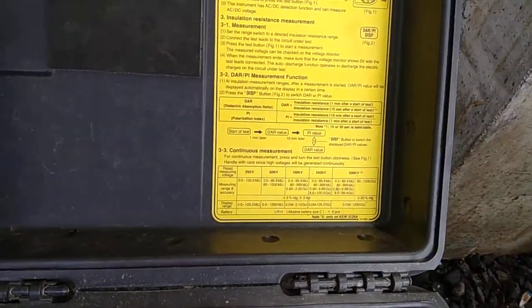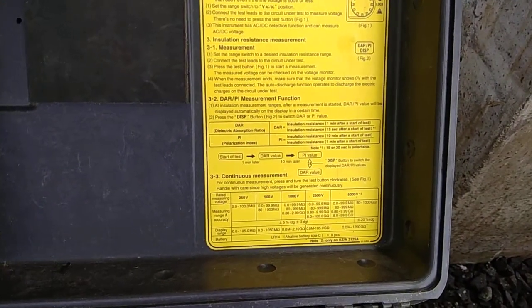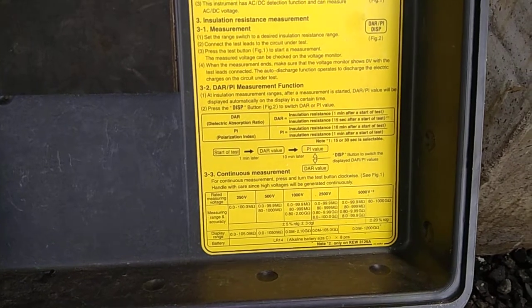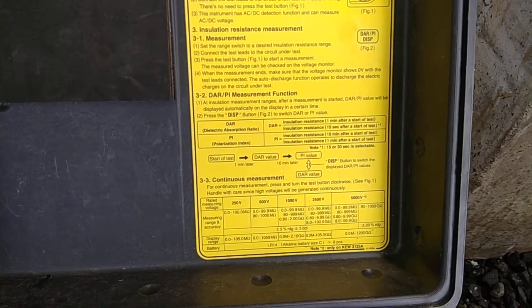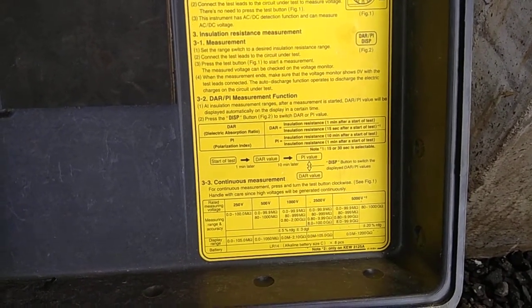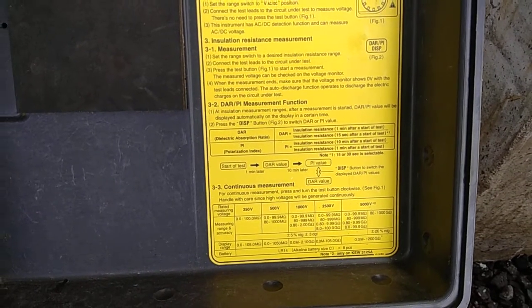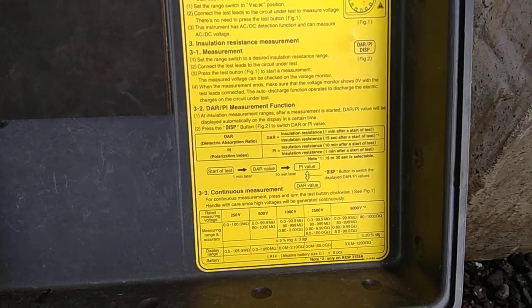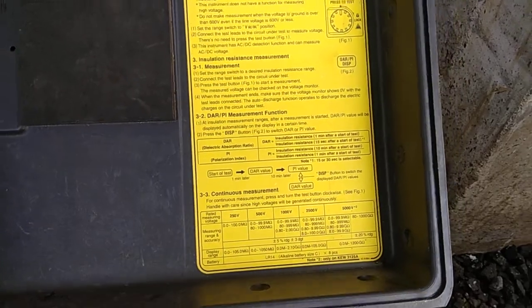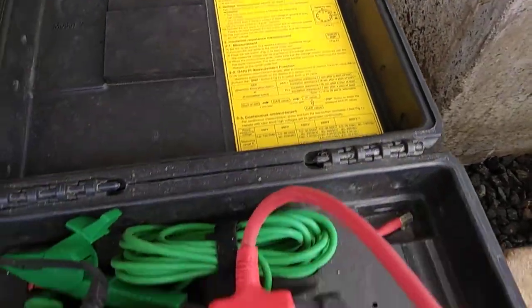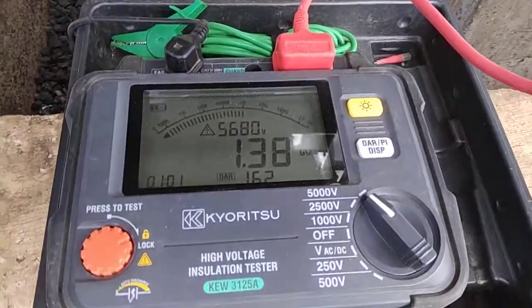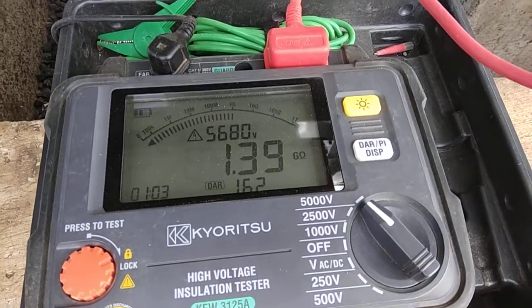DAR. So if you see carefully, here DAR is mentioned: dielectric absorption ratio. It is the ratio of the resistance after 1 minute to 15 seconds, and PI is the same thing, but it is the ratio of the resistance after 10 minutes to 1 minute. So coming back to the question, why are these tests conducted for 1 minute and 10 minutes?